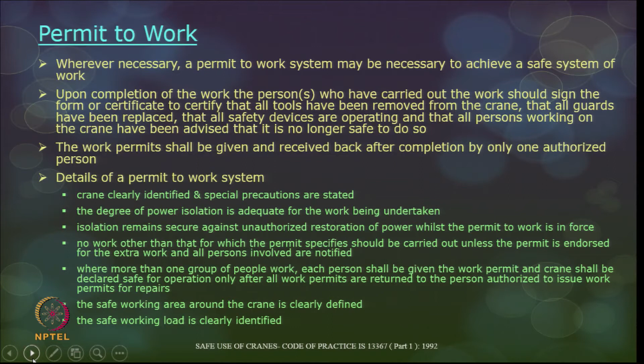Now, the details of a permit to work system: the crane is clearly identified, the special operations and precautions are all mentioned, and the degree of power isolation is adequate for the work being undertaken. Isolating the equipment means securing against unauthorized restoration of power whilst the permit to work is in force. The safe working load around the crane is identified and clearly understood. Where more than one group of people is working, each person should be given the work permit, and the crane should be declared safe for operation, and only then shall the crane operation start.